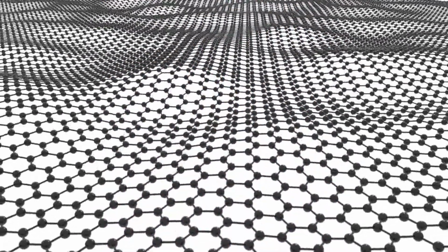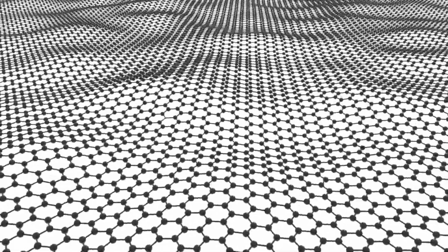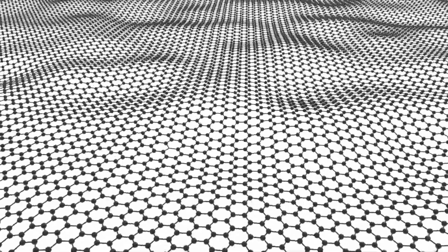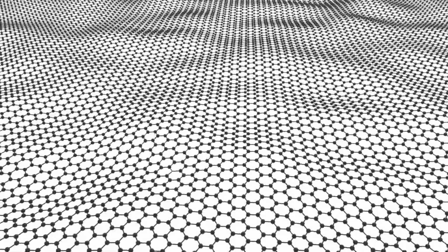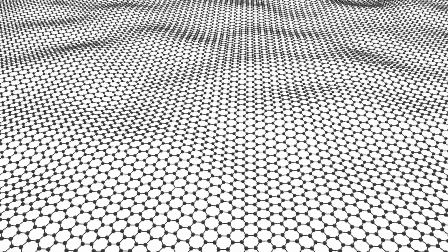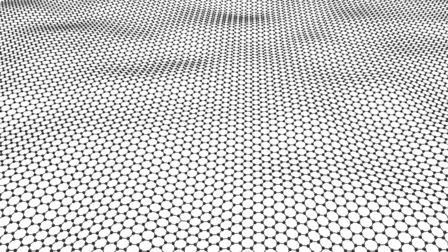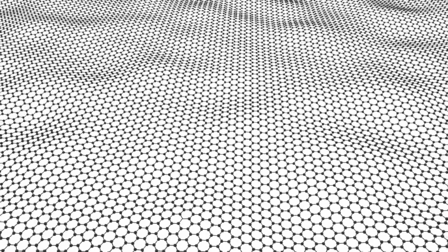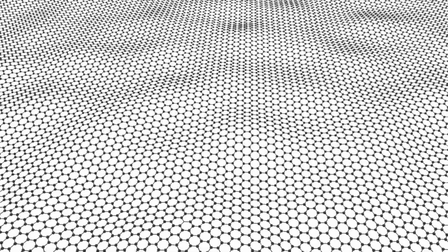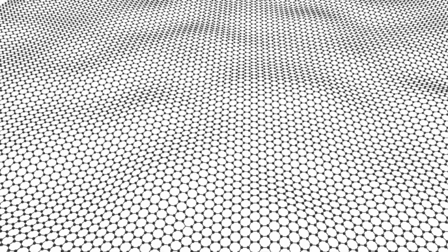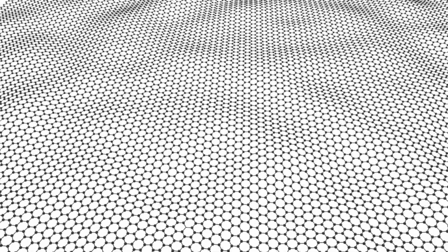Here we use suspended single-layer graphene as our substrate because it allows us to see every atom. When we operate the microscope with an accelerating voltage above the displacement threshold for graphene, we can directly eject carbon atoms from the lattice. When we operate below the displacement threshold for graphene, we can preserve the integrity of the pristine lattice and investigate more subtle changes without continually damaging the specimen.